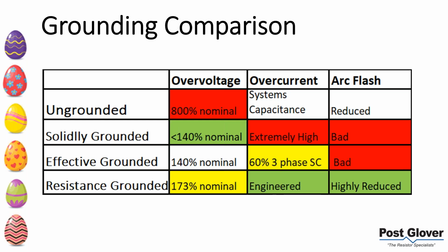Effective grounded, if you haven't seen that before, it's trying to be solid ground without being solidly grounded, essentially, I guess is what I would say. So you have a lower current. You're reduced to 60% of your three-phase short circuit current. Your voltage is a little bit higher, but still acceptable, I believe, especially for certain electronics. 140 should be okay. So once again, there's still a lot of energy, a lot of potential for arc flash.